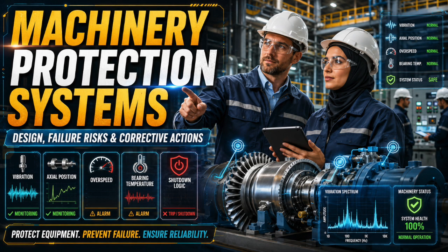Set point multipliers matter. They can be useful during startup in specific cases, but they are dangerous if used casually. If you multiply set points simply to avoid nuisance trips, you may be weakening protection when the machine is vulnerable. A set point multiplier must be justified, controlled, indicated, logged, and reviewed. If it is active, operators must know it. If it is not needed, do not use it. Do not desensitize protection to hide poor design. Fix the design, fix the installation, fix the machine, fix the measurement.